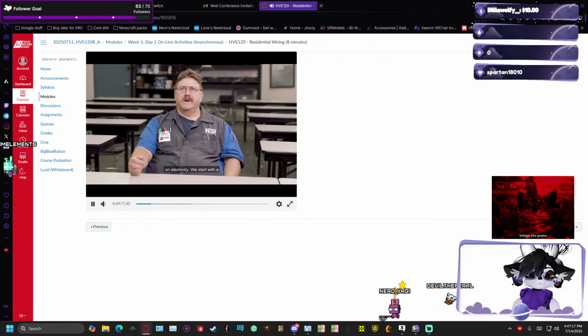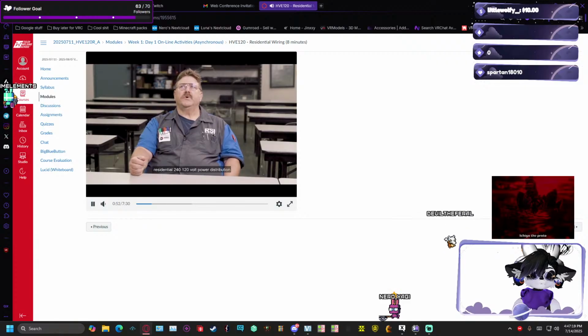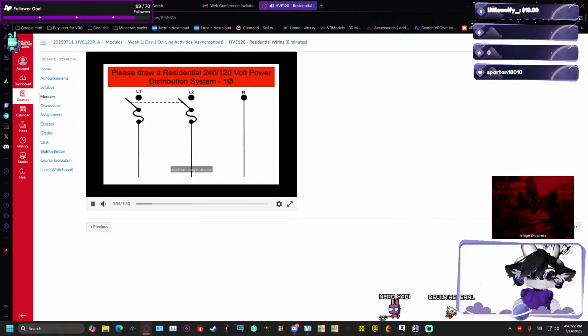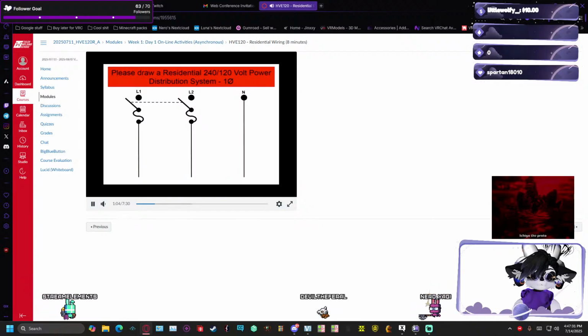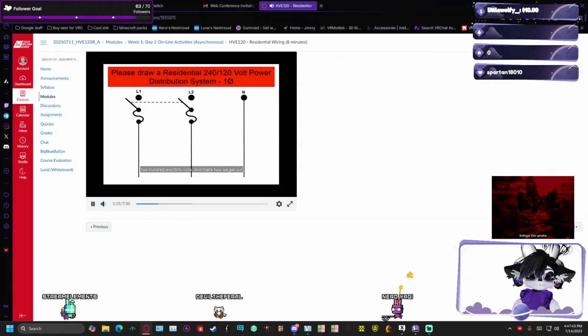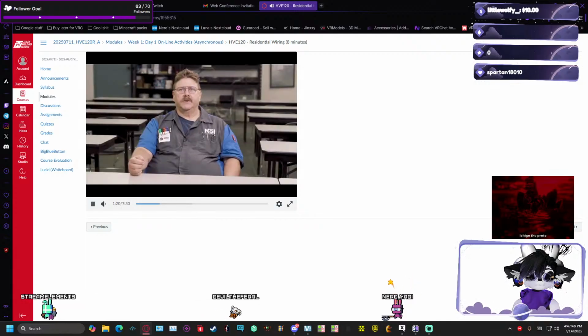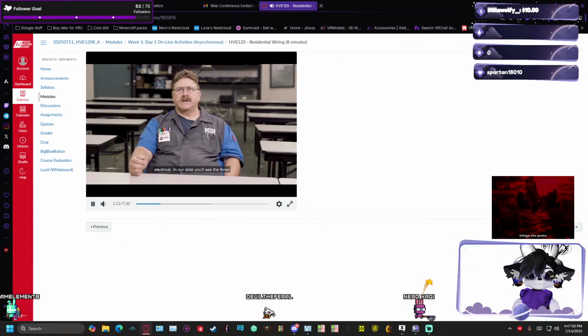We're going to start with a residential 240/120 volt power distribution system, single phase, as you can see on the PowerPoint. When we talk about residential electricity, we have single phase, which is L1, L2, and a neutral. L1 is 120 volts, L2 is 120 volts, and the neutral is our balancing. So from L1 to L2 is 240 volts, and that's how we get our power to our distribution for our home electrical.